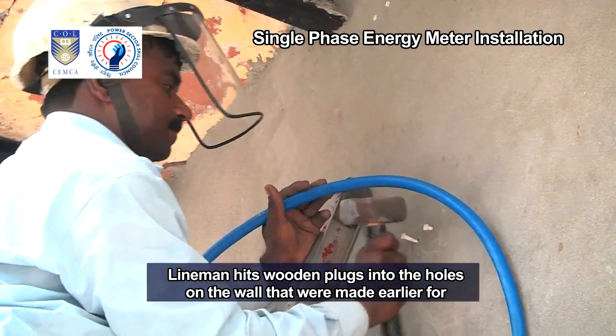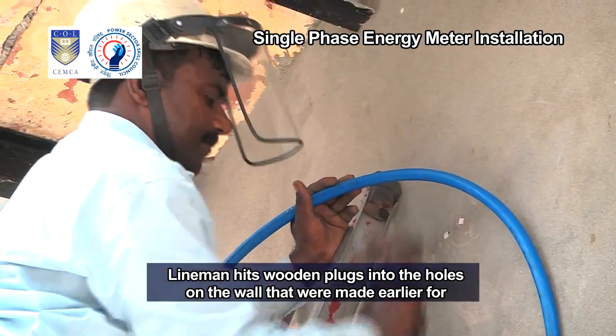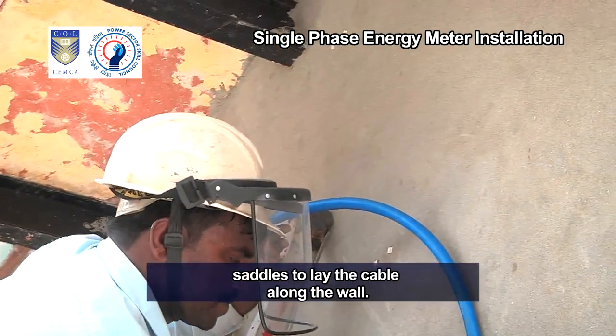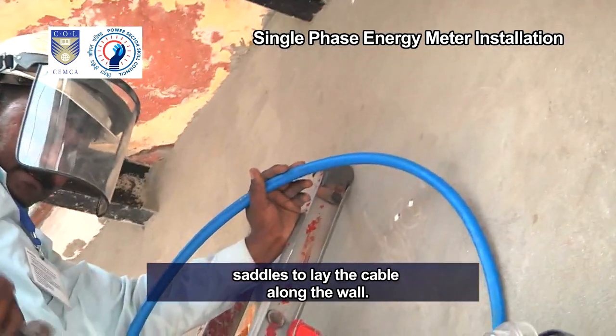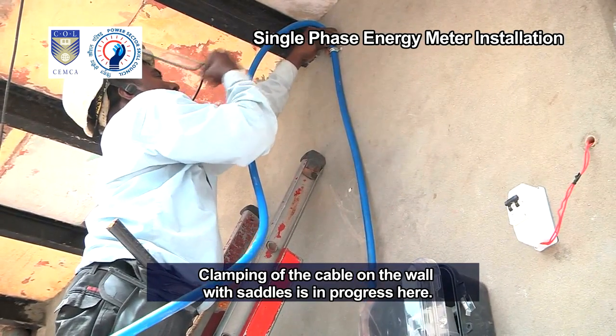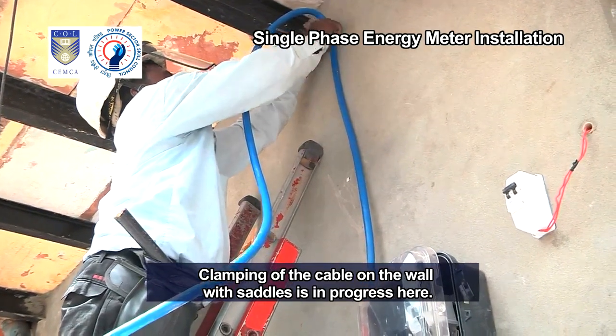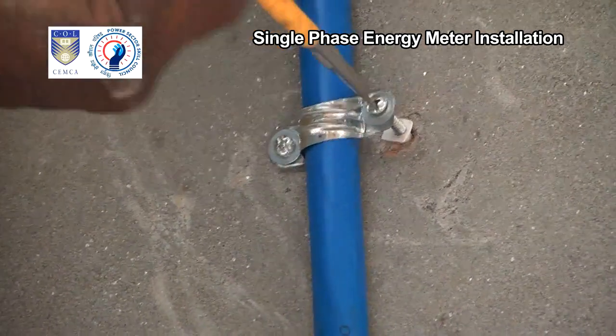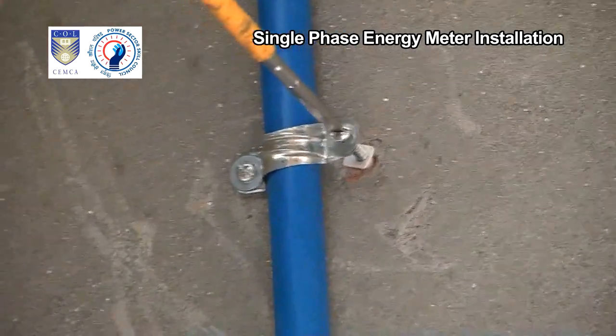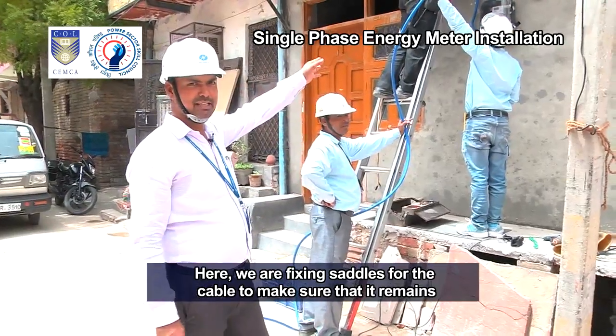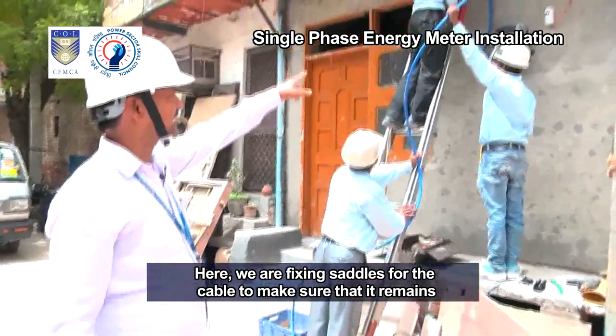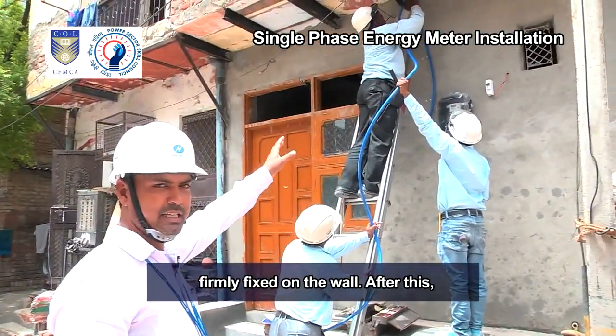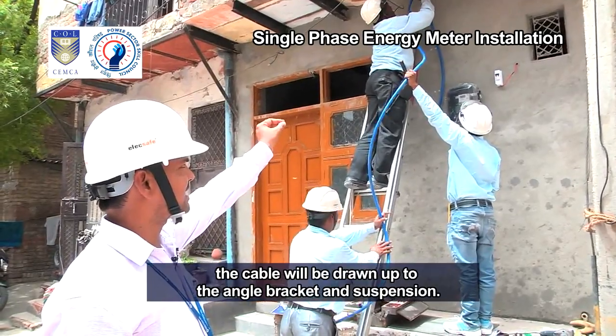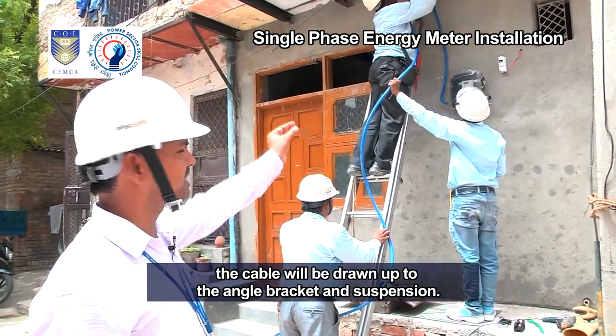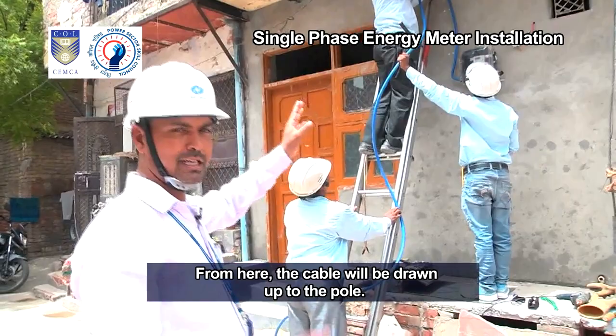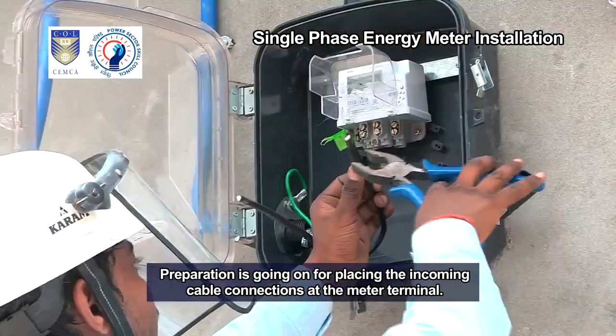Lineman hits wooden plugs into the holes on the wall that were made earlier for saddles to lay the cable along the wall. Clamping of the cable on the wall with saddles is in progress here. Here, we are fixing saddles for the cable to make sure that it remains firmly fixed on the wall. After this, the cable will be drawn up to the angle bracket and suspension. From here, the cable will be drawn up to the pole.